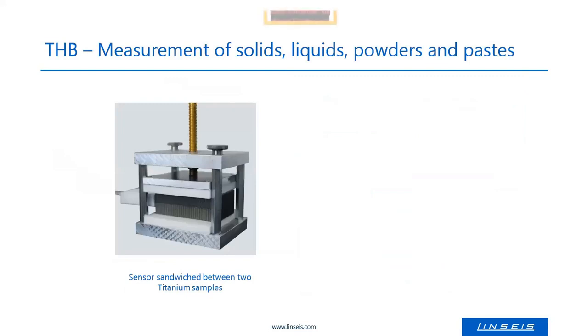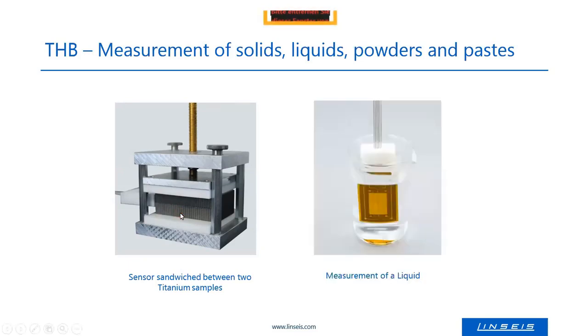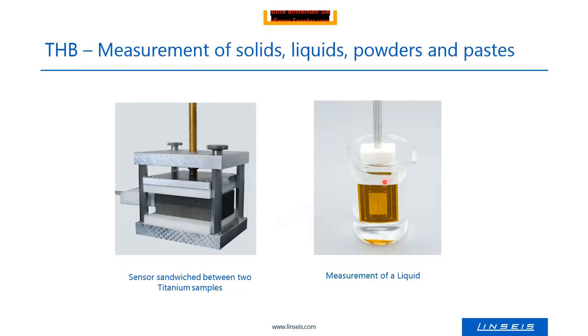The setup when you measure solids requires sandwiching the sensor between two sample halves — one on the top and one on the bottom — then applying a weight or pressing with a suitable device. For liquids, you can just put the sensor into the liquid. We also have special sensors with a metal frame around them for viscous liquids, pastes, powders, or loose samples that need the sensor stabilized.